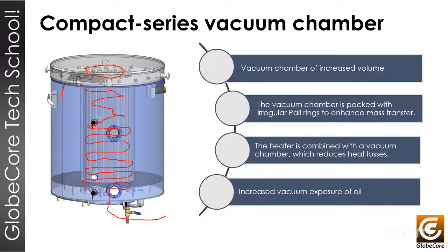And this machine has another really important feature, which is the use of irregular pall rings. We can see here that these pall rings are a lot of plastic rings inside the vacuum chamber, and they make it so the oil coming from the top of the chamber will not have a direct path from the top to the bottom of the vacuum chamber.